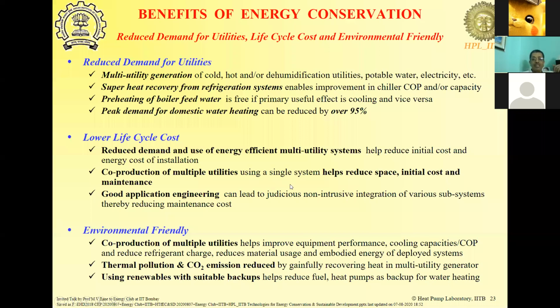So multi-utility heat pumps can reduce the initial cost as well as the energy consumption and operating cost, and it can reduce the space requirement. It can also reduce the maintenance requirements for this particular system. Proper application engineering, however, has to be done so that you select a suitable size and don't oversize it, so that the paybacks are good.